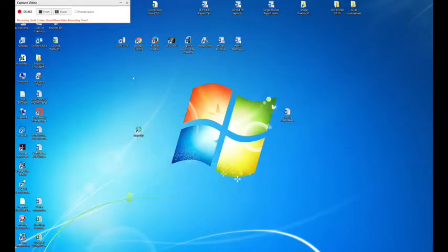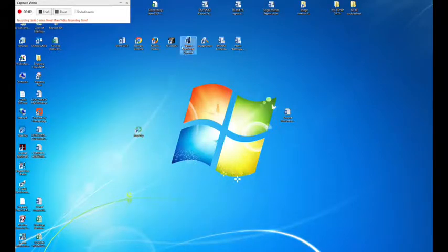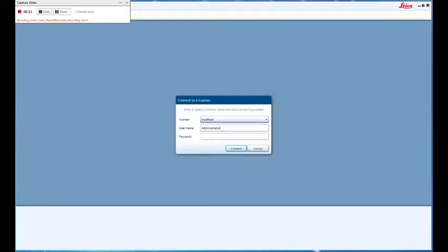Hey guys, it's Jacob here. I'm going to give you a tutorial on how to load the Aperio instrument. Start off by clicking the Aperio button there and entering in the username, which is administrator, and password is scanscope, and click connect, which will bring you to the screen.